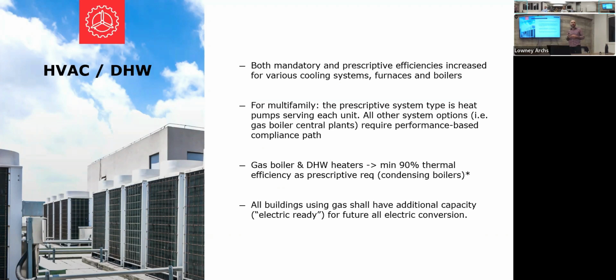So if you want to use a gas boiler, if you're in a city that doesn't have that REACH code, and the owner says, no, I want to stick with a gas boiler for my building, then you would have to do some performance calculation because the prescriptive system type is heat pump. For gas boilers and domestic hot water heaters, if you install them, the minimum thermal efficiency is now 90%. And that means the equipment needs to be condensing type to get to that efficiency. You can't get to that efficiency with non-condensing gas-fired equipment.